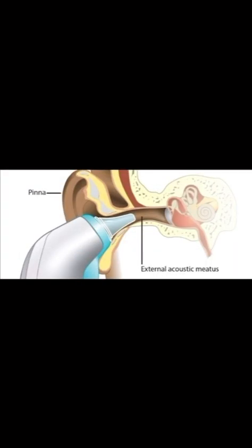Care should be taken when using the tympanic thermometer, as poor technique can render the measurement inaccurate. Temperature differences between the opening of the ear canal and the tympanic membrane can be as much as 2.8 degrees Celsius.